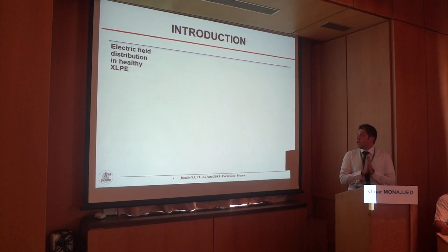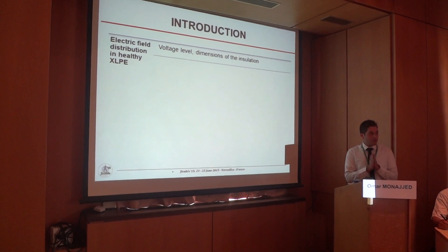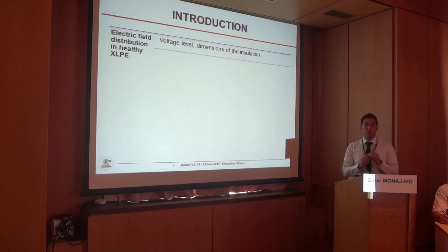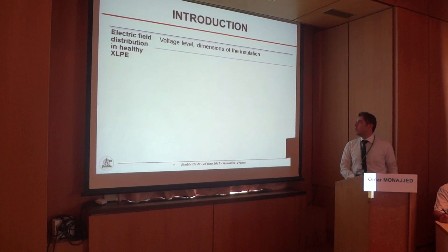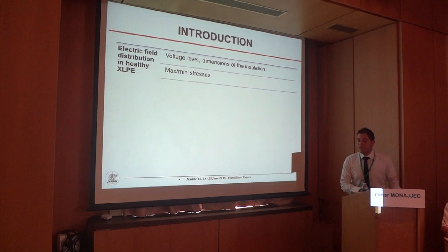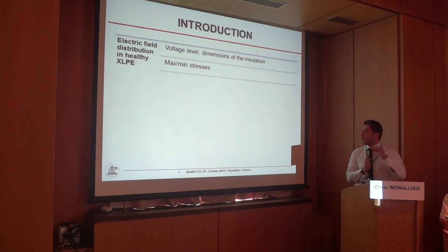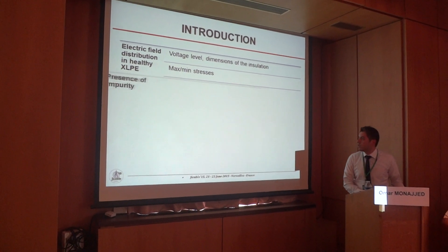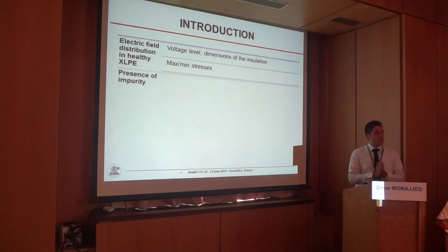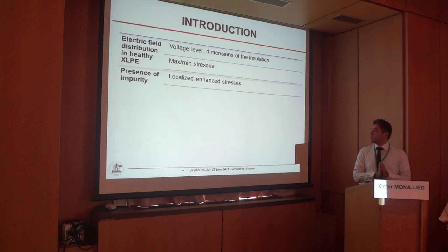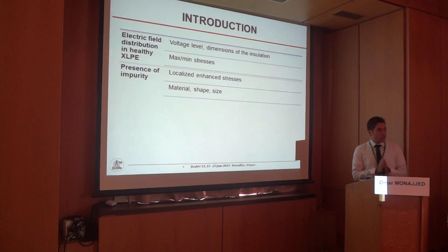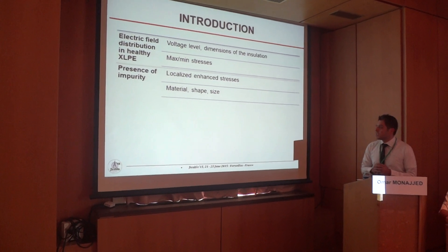For the introduction, the electric field distribution in healthy XLPE depends first on the voltage level and on the dimensions of the insulation — the diameter under insulation and the diameter above insulation. We get maximum stress on the inner semi-con insulation interface and minimum stress on the outer semi-con insulation interface. Now, in the presence of impurity, we will have localized enhanced stresses. These stresses will depend on the material of impurity — its permittivity — and also on the shape of impurity.